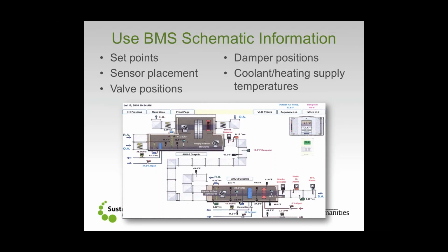We want to be able to look at it and say, all right, if we have valve positions available to us for different coils, whether they be cooling coils or heating coils, on a hot summer day, if we go in and look at that BMS and we're trying to dehumidify, then we might expect to see the cooling coil valve 100% open. And if we don't, that's a good time to start asking questions about whether we could do better with dehumidification if it was. And also looking at damper positions, not just in terms of outside air and return air, but also thinking about the potential for face and bypass. Where is the air being routed to, and how are the dampers that decide that controlled? What makes up that decision? Or do they just sit in the same spot all the time?